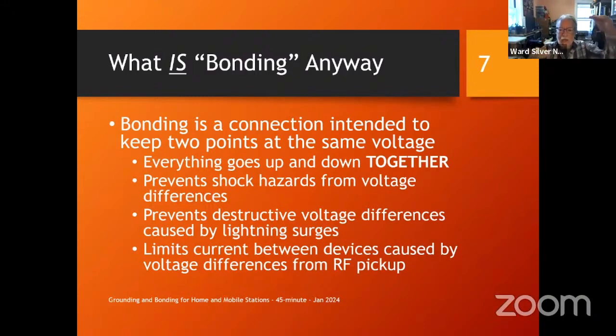That prevents shock hazards from voltage differences. If there's a fault, it prevents these destructive voltage differences caused by lightning surge when point A goes to 10,000 volts over point B just for a second. But lightning's really fast and it can create really serious destructive surges of current between the equipment. So by minimizing the voltage differences, you minimize the lightning surge voltage and current.